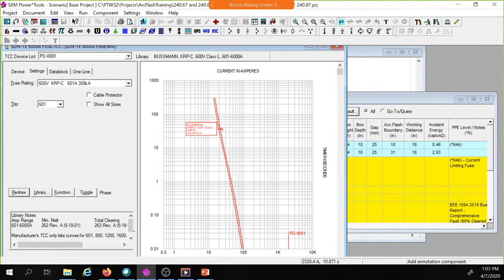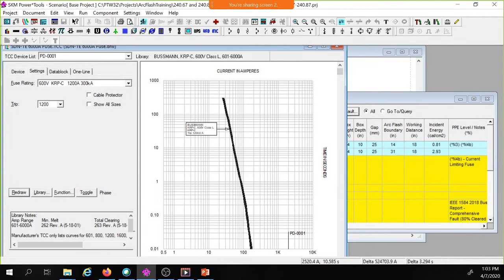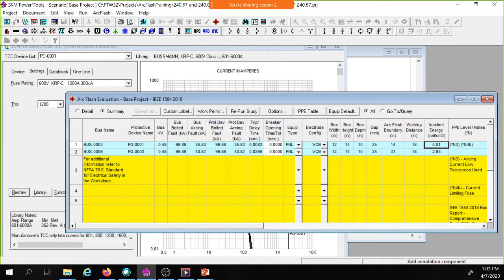This is my fuse curve. I'm going to move this curve to the right. I'm putting in a 1200 amp fuse. My incident energy went up to 0.81. My clearing time went up to 0.0083.